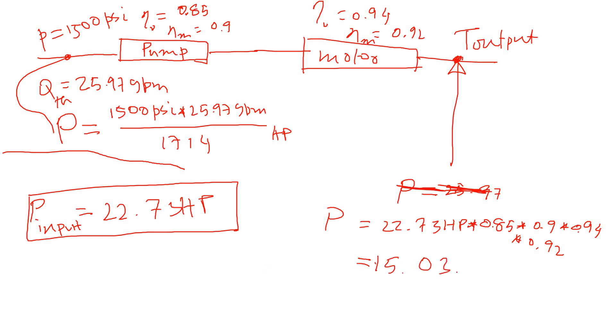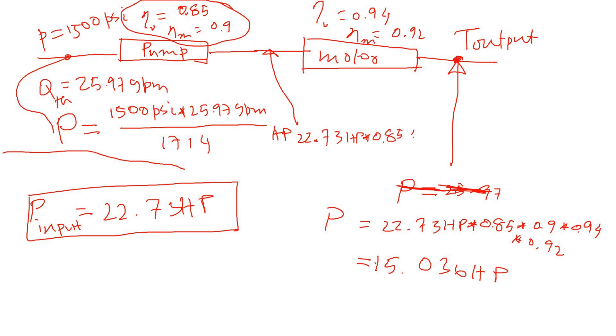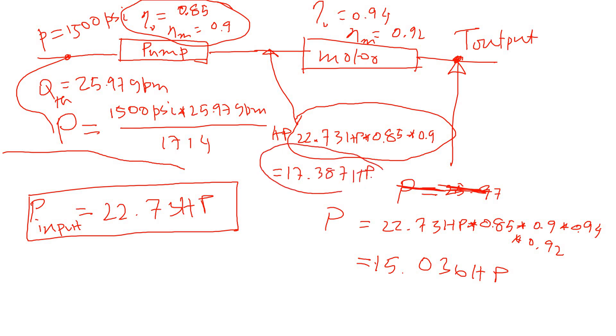The total power output at the motor shaft I calculated is 15.036 horsepower. If you're interested in the power between the pump and the motor, that uses only the pump efficiencies: 22.73 hp × 0.85 × 0.90 = 17.387 horsepower. That is the power output by the pump and the input to the motor.